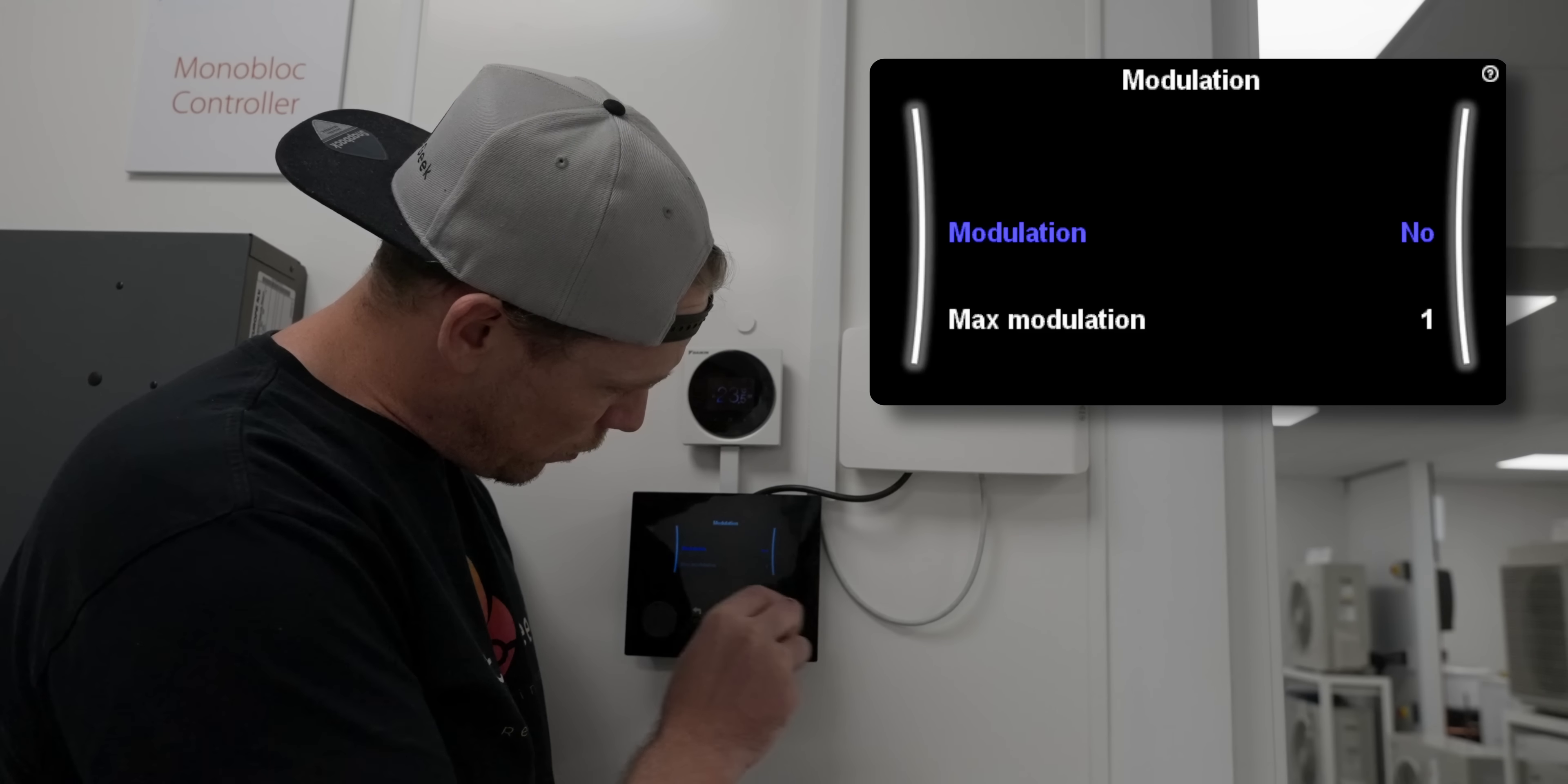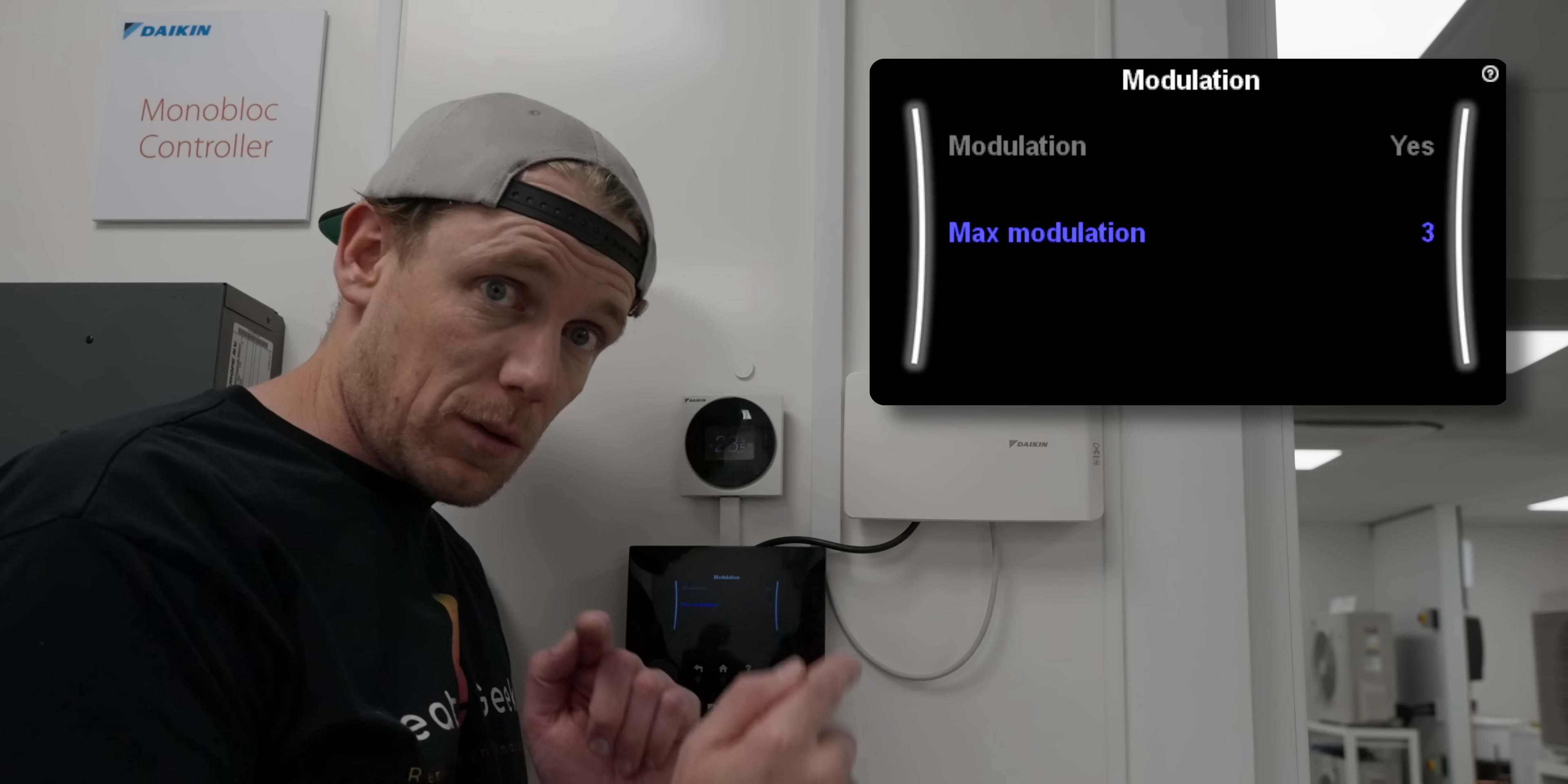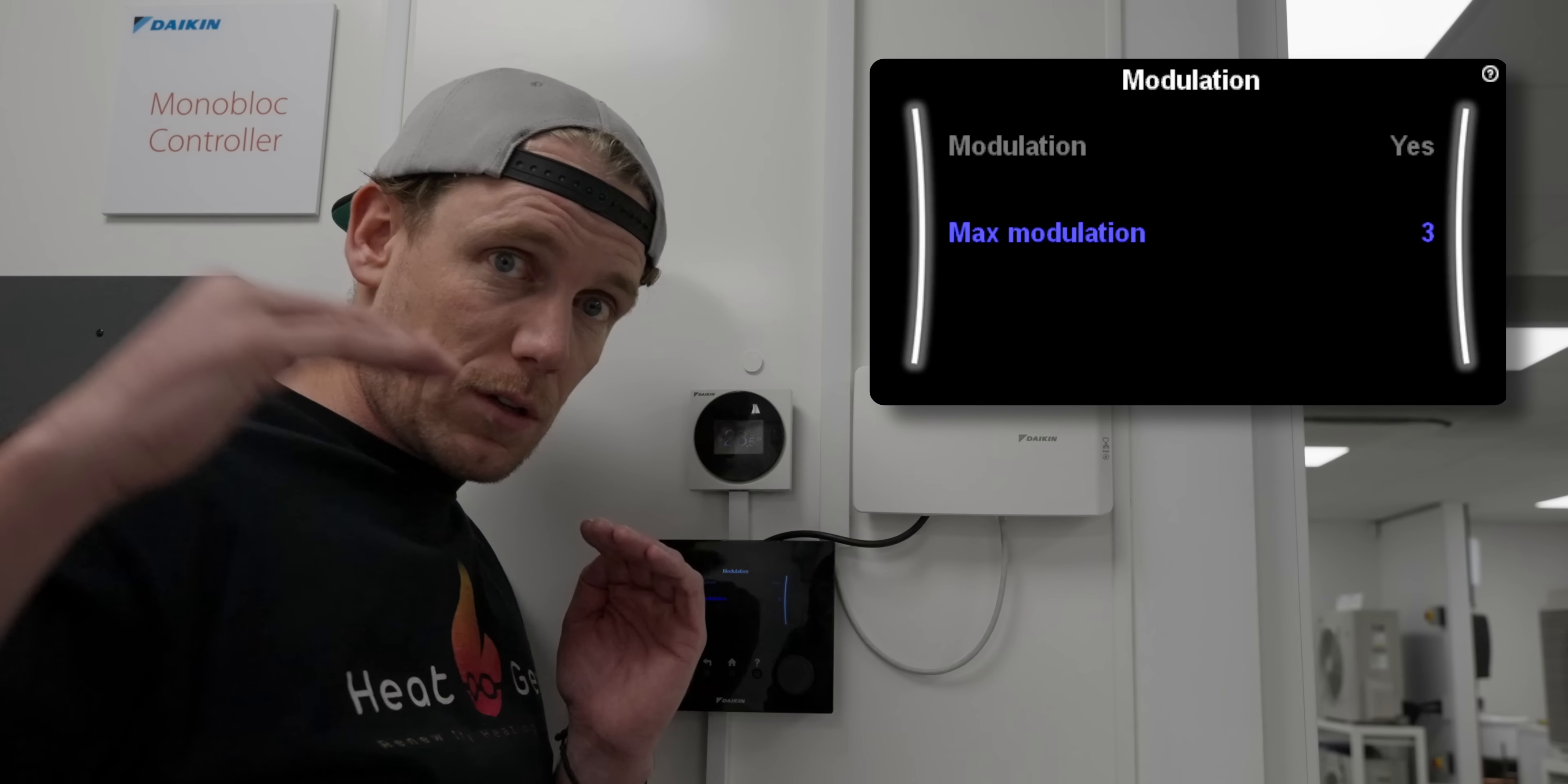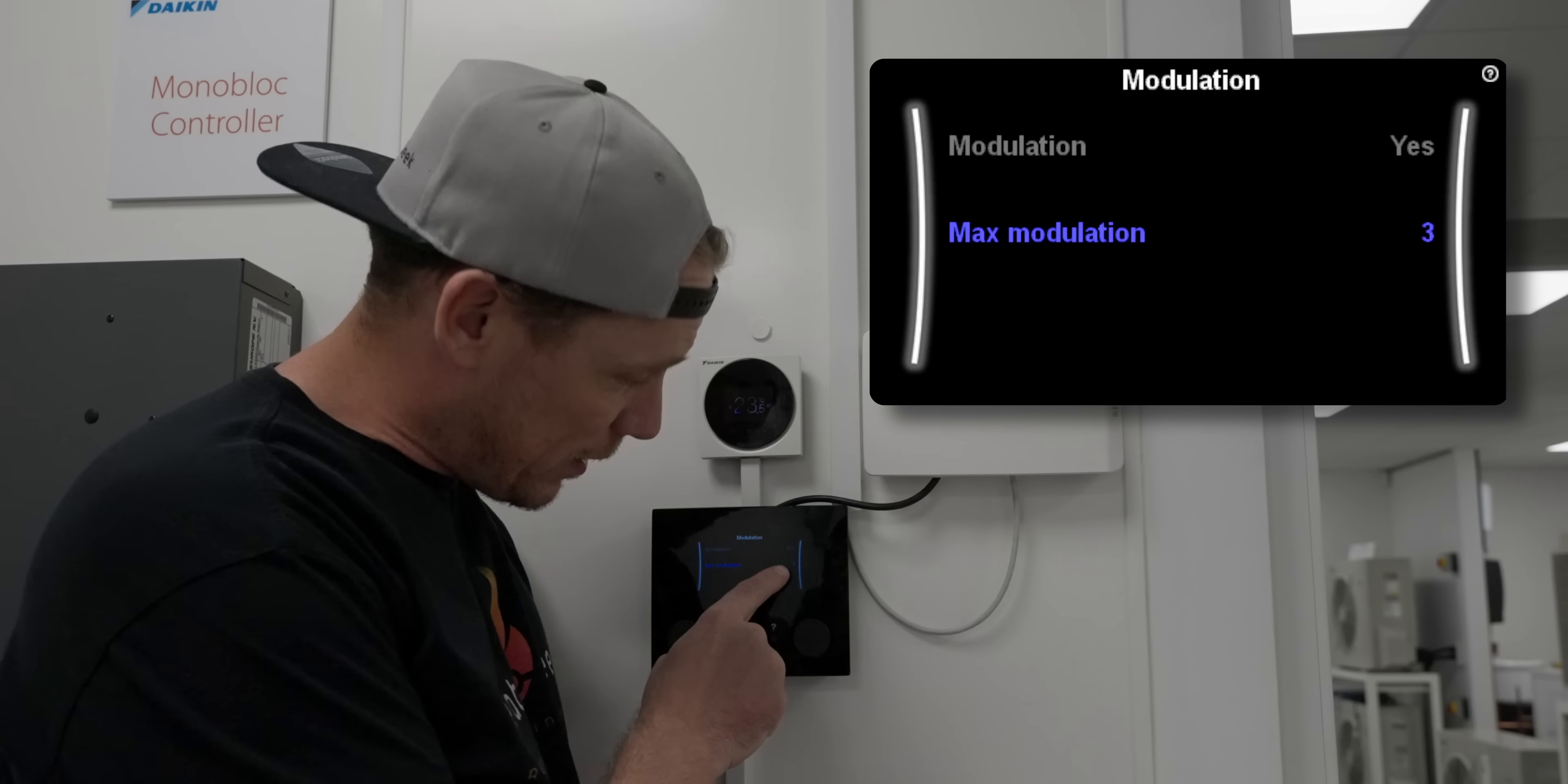We can change the no to a yes. Now we can turn this dial and rather than once we've got the weather compensation perfect, pulling in the external third party thermostats down to act like a brake, instead we can rely on this to shift the flow temperature off the weather compensation curve by different amounts of degrees in order to refine the correct flow temperature for the house to get a perfect room temperature.